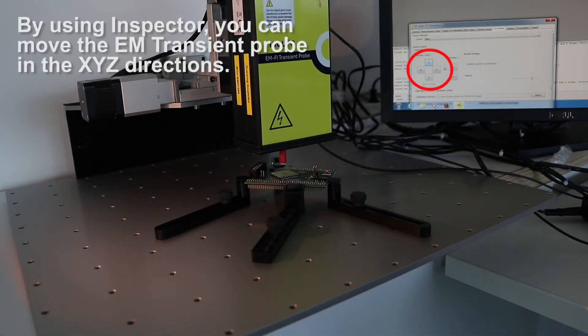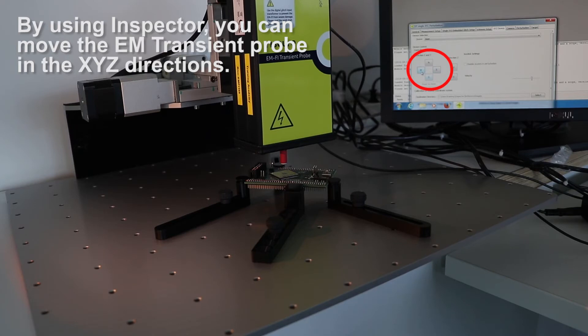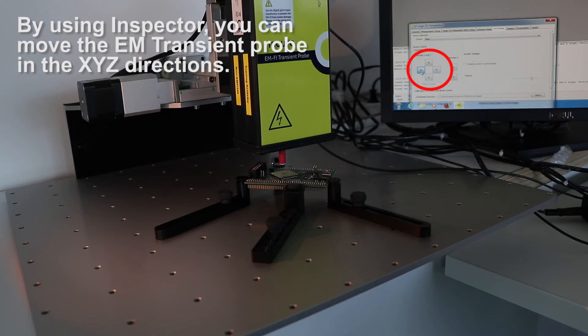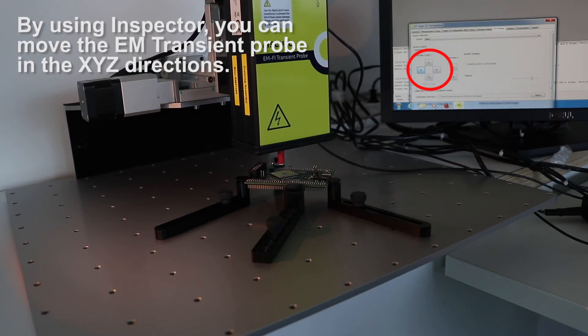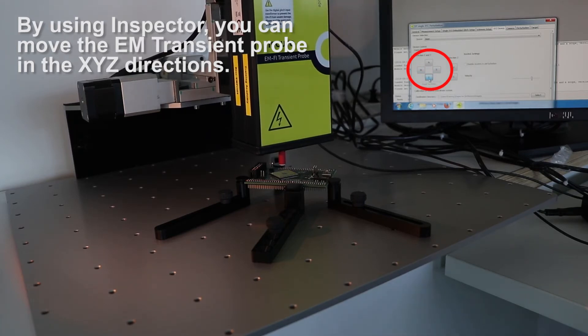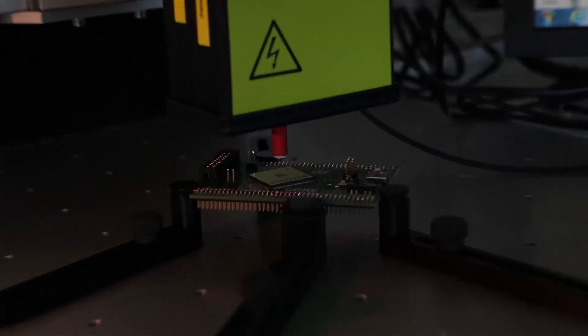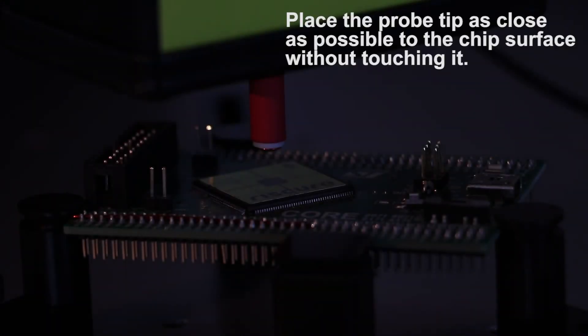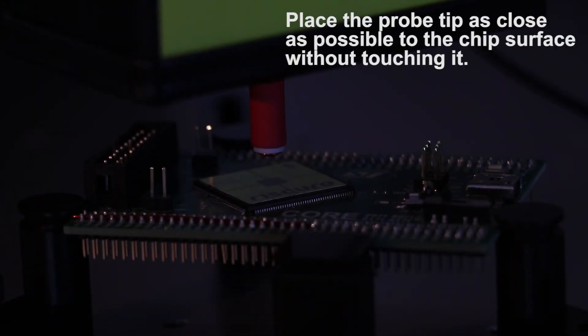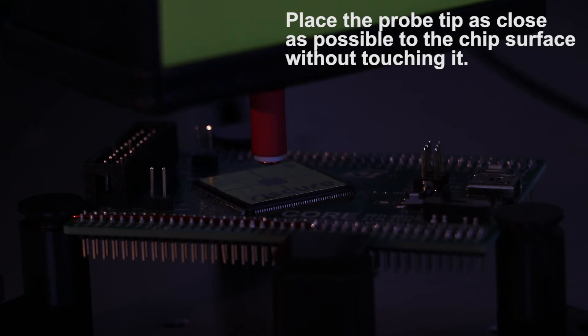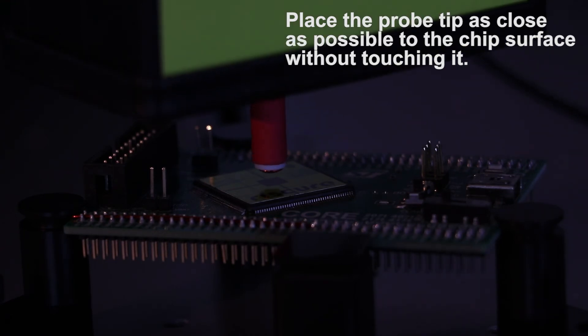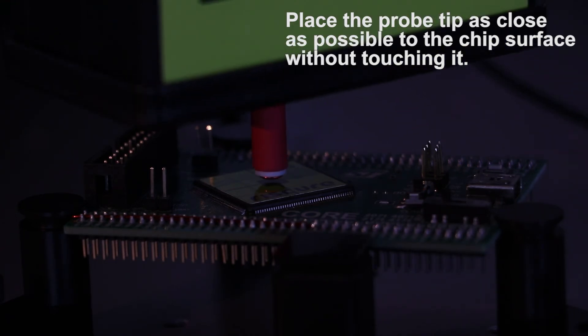Finally, you need to place the transient probe to the correct spot. To do that, move the probe with precision in three dimensions using Inspector. Be careful. You need to place the probe tip as close as possible to the chip's surface without touching it.